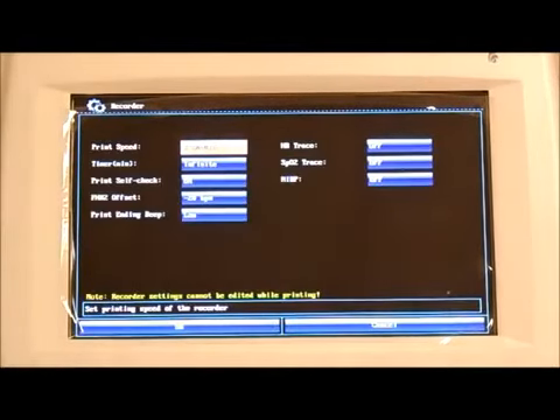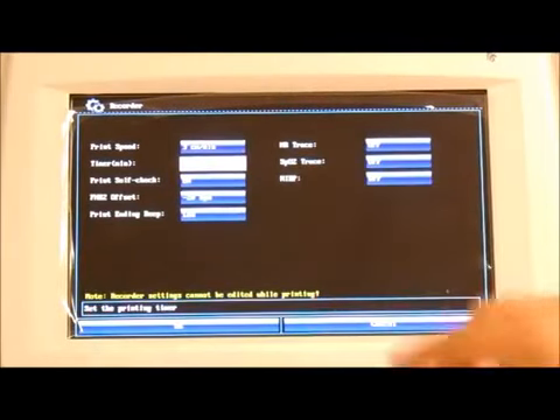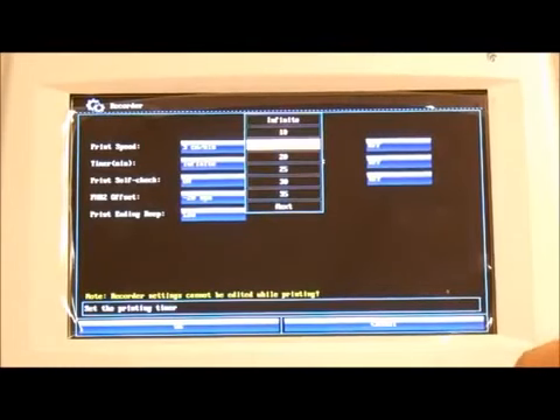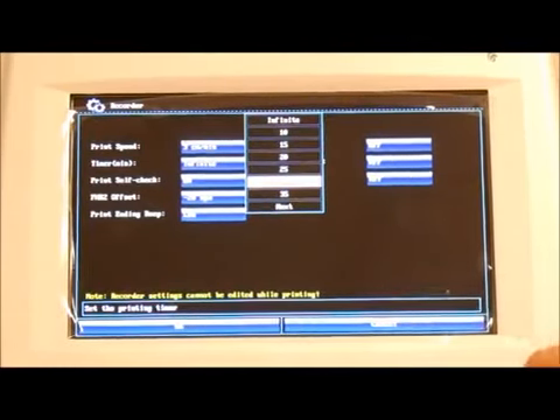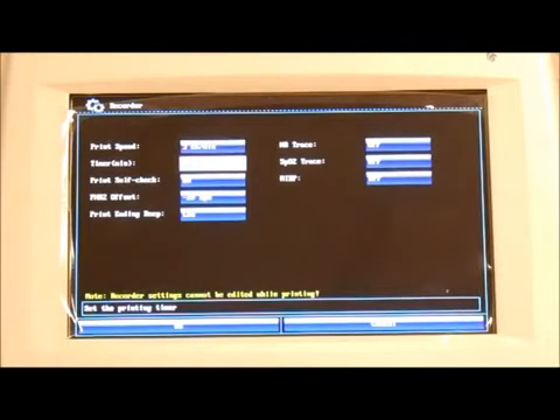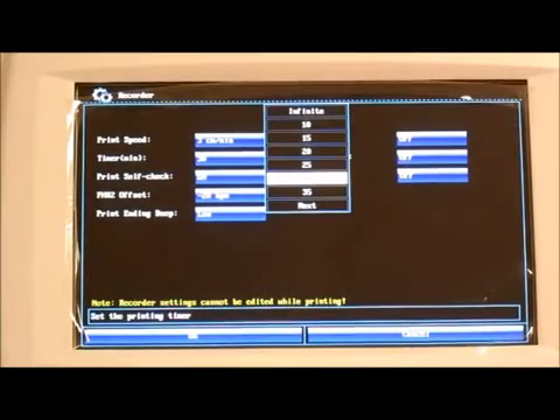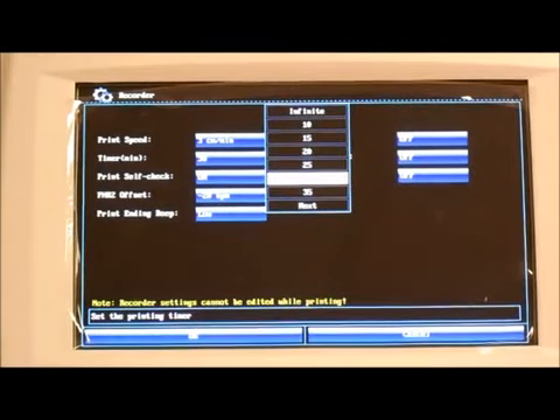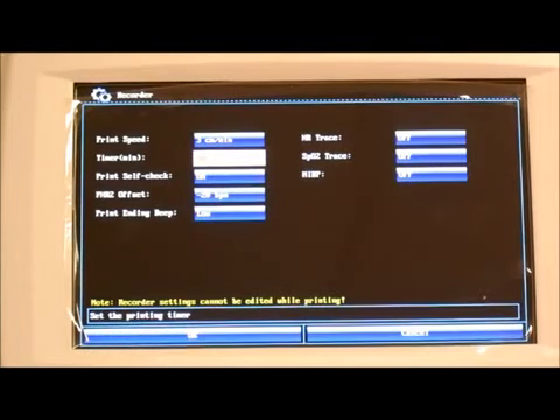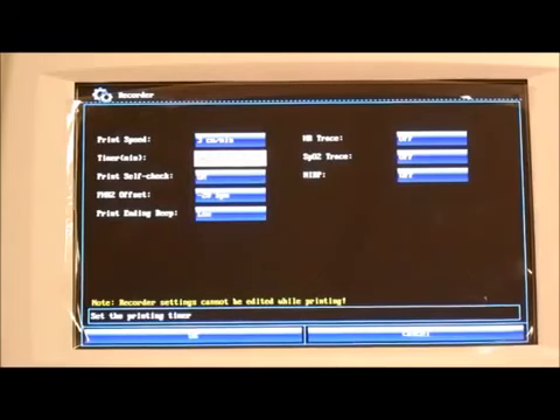Okay, next we have the recorder. We can set the print speed, which is 3 centimeters per minute, the standard setting, and the timer. The current timer setting is infinite, which means that the monitor will start printing and keep going until you press the start key. But if you select a numerical value, for example 30, the monitor will start printing, and after 30 minutes it'll stop by itself. So for the timer setting, if you set a numerical value, this is your time period. So 30 would mean 30 minutes.